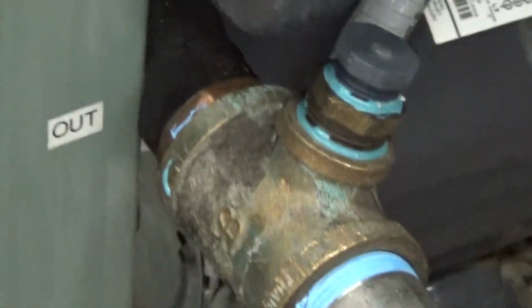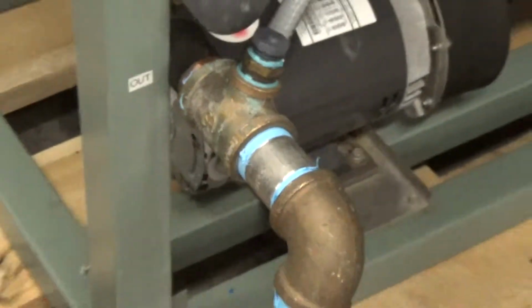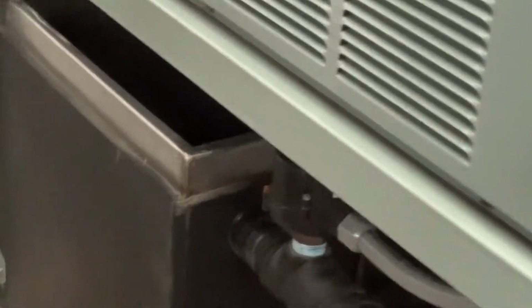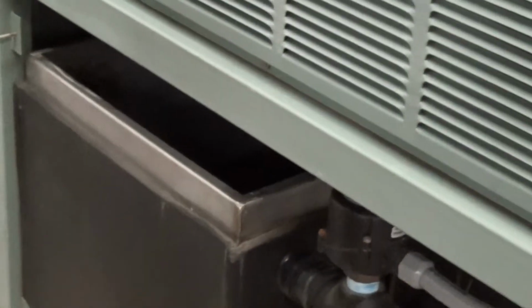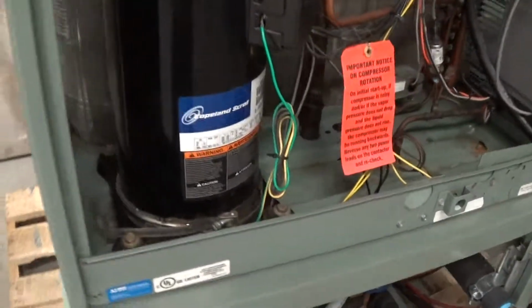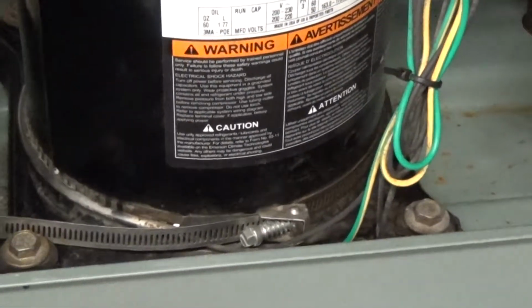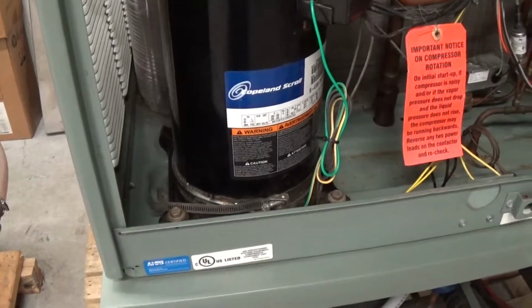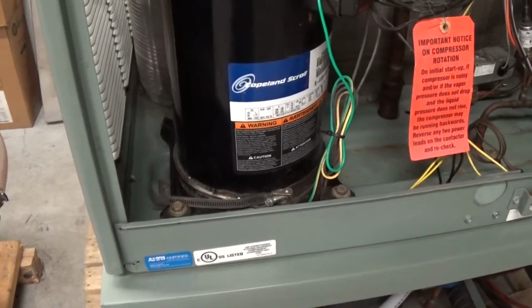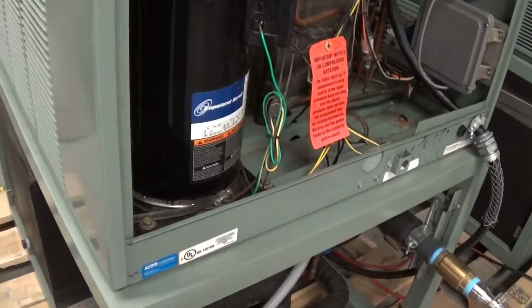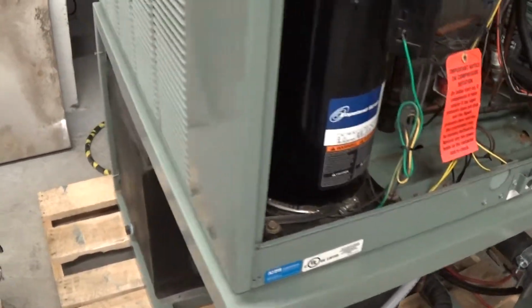This cap here stays on for your application. That's the lower one, that's your out to process. And we do have the stainless lid for the tank. The compressor does have a crankcase heater. As soon as you put power to the chiller, that's always on. We recommend at least 12 hours. I think the manual says 24 hours of that crankcase heater on to make sure the refrigerant's not too cold before you first start it up.